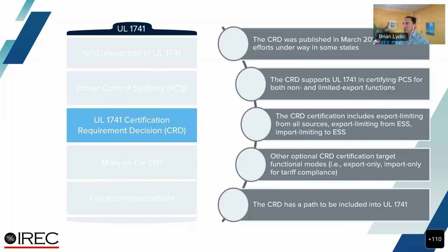We're just going to focus on the power control systems CRD. It allows you to certify these power control systems for non-export and limited export functions, and as I mentioned before, they can be certified for the National Electrical Code use case of limiting currents on a conductor, as well as the interconnection use case of limited export. Then there's import limiting, and other optional modes can offer NEM tariff compliance. So you can export limit from all sources, or export limit just from the energy storage, or import limit to the energy storage — four different modes. Then there's export only, import only, unconstrained, and I think there's one more I'm not sure what I'm missing there.